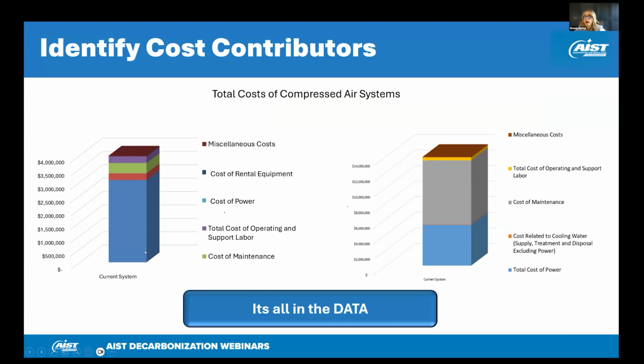This picture on the left graphically represents that about 75% of the cost of ownership of this compressed air is spent in power. That is ideal. This is typically not the case when we data log all the information from a mill. We find where maintenance and rental compressors may be the largest cost of their compressed air system. So then they can start to fine tune and address the areas for improvement and realize power savings and cost savings. But really we want to see people measuring what they manage and understanding a baseline.